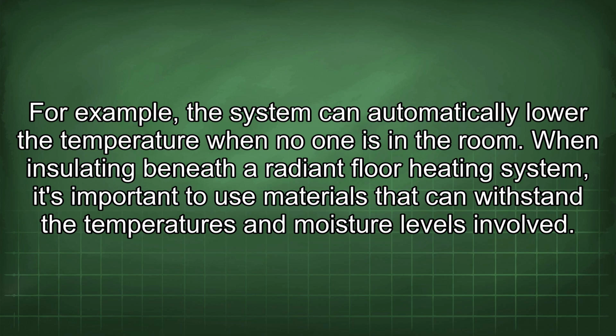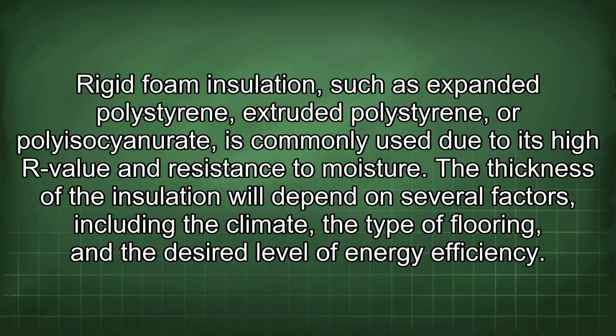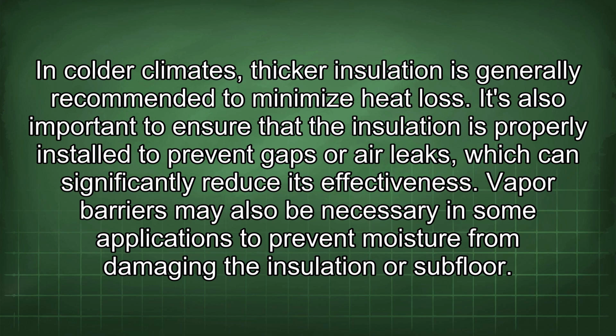When insulating beneath a radiant floor heating system, it's important to use materials that can withstand the temperatures and moisture levels involved. Rigid foam insulation, such as expanded polystyrene, extruded polystyrene, or polyisocyanurate, is commonly used due to its high R value and resistance to moisture. The thickness of the insulation will depend on several factors, including the climate, the type of flooring, and the desired level of energy efficiency. In colder climates, thicker insulation is generally recommended to minimize heat loss. It's also important to ensure that the insulation is properly installed to prevent gaps or air leaks, which can significantly reduce its effectiveness.